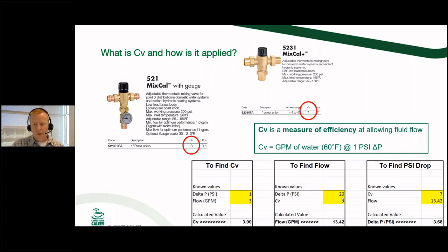So you want to avoid that if at all possible, especially when you start looking into those big raining showers with the body sprays and all that other fun stuff. You want to make sure to limit that pressure drop. Now, in this next scenario, you've got a CV of 7, which is this big 5231 series valve. You take that same flow, 13.42 gallons per minute, again not unheard of for one inch copper piping. And now, instead of getting a 20 PSI drop, you're getting a 3.68 PSI pressure drop, which is very manageable. It's something that you're going to want. It's not out of this world as far as the pressure drop.